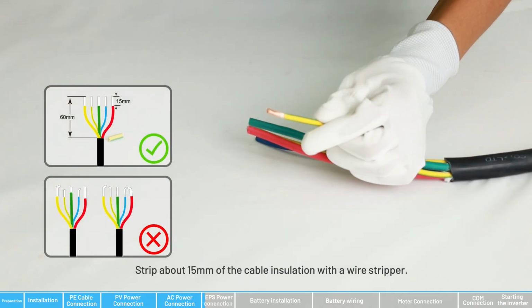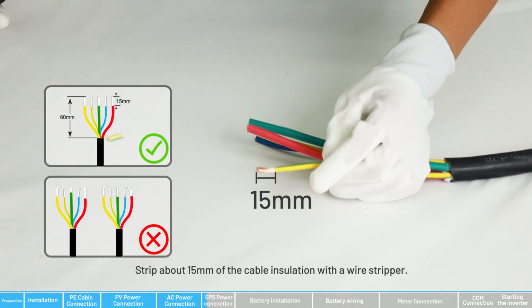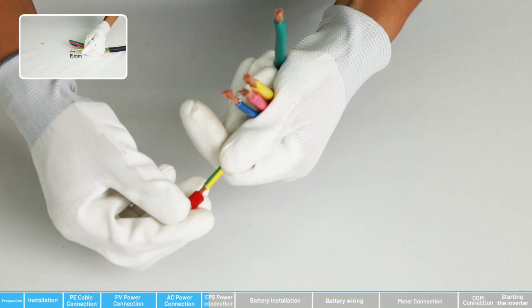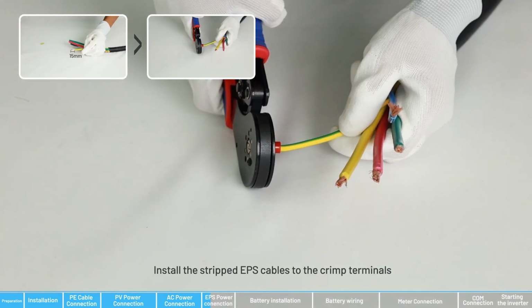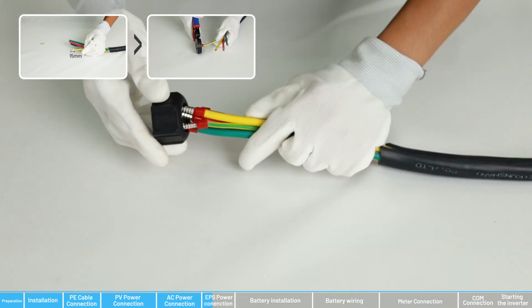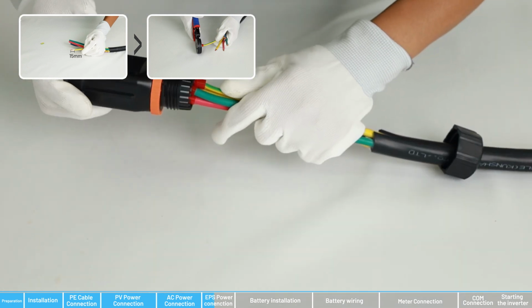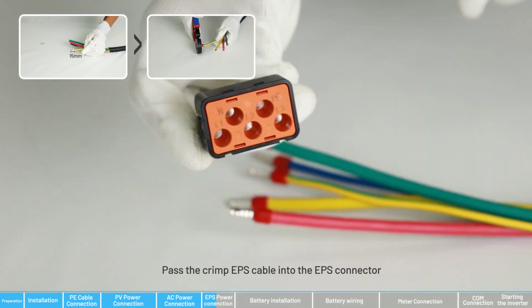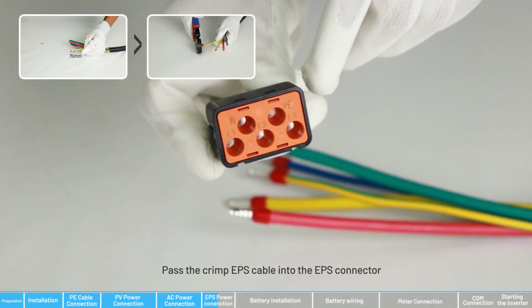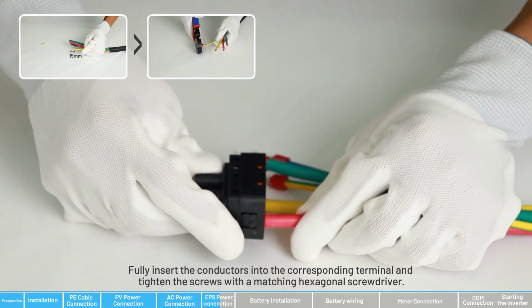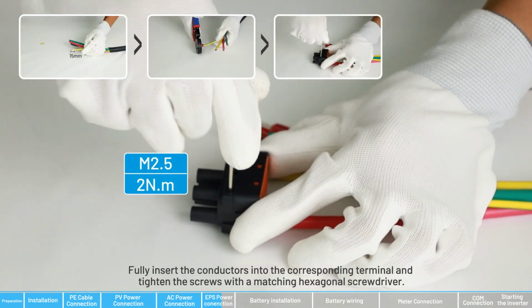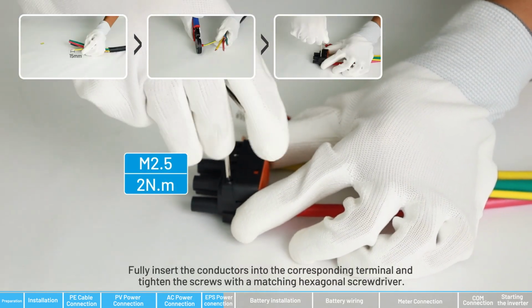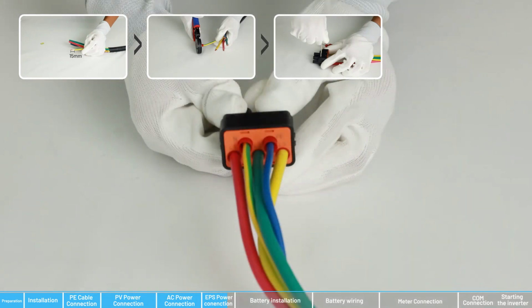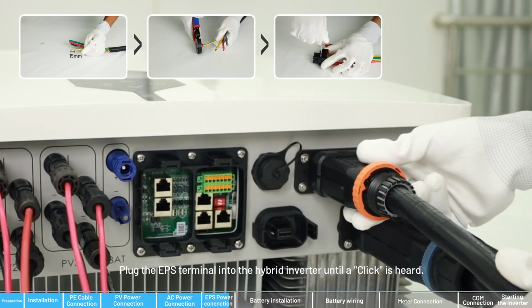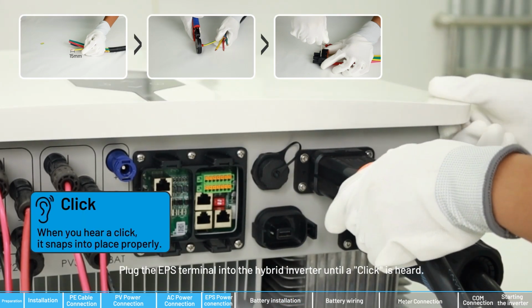Strip about 15 mm of the cable insulation with a wire stripper. Install the stripped EPS cables to the crimp terminals. Pass the crimped EPS cable into the EPS connector. Fully insert the conductors into the corresponding terminal and tighten the screws with a matching hexagonal screwdriver. Plug the EPS terminal into the hybrid inverter until a click is heard.